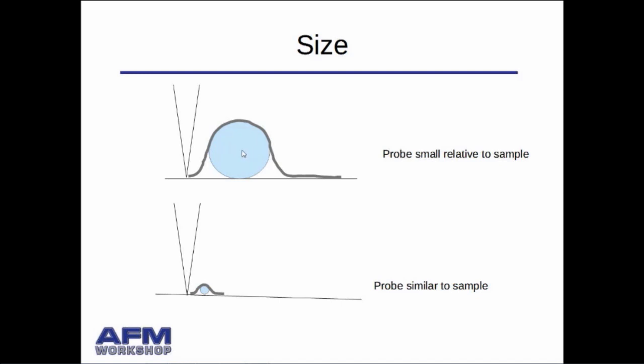If the probe is much smaller than what you're trying to measure, then you can get a pretty accurate measurement. But if the probe is on the same order of magnitude as what you're trying to measure, as in this case, you'll get an artifact which is a combination of the probe and the sample geometry. So again, selecting the probe really is important to understand what the size of what you want to look at is.